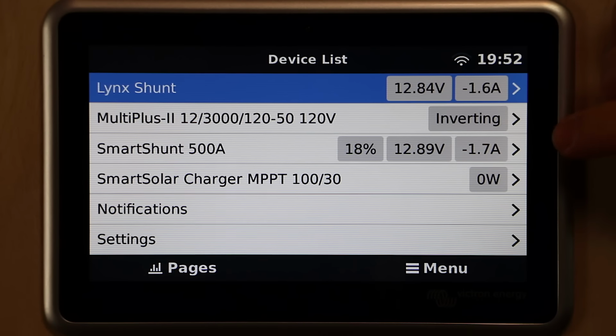On voltage, you can see it says 12.89 volts on the SmartShunt, and that's what the multimeter reads if I measure the SmartShunt terminals between battery positive and the SmartShunt — we'll get about that voltage. Then at the Lynx Shunt, with no current flowing right now, or very little, the voltage there should read the exact same as the SmartShunt, but the Lynx Shunt is reporting 0.05 volts less for the same voltage. So it's a little bit off on that.